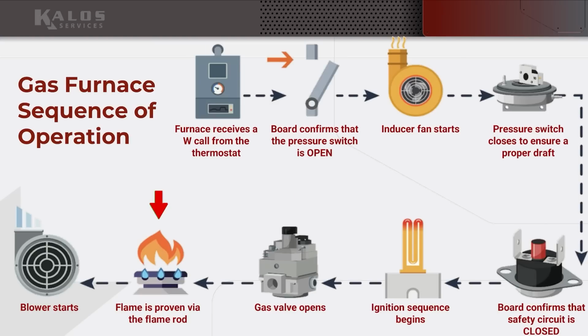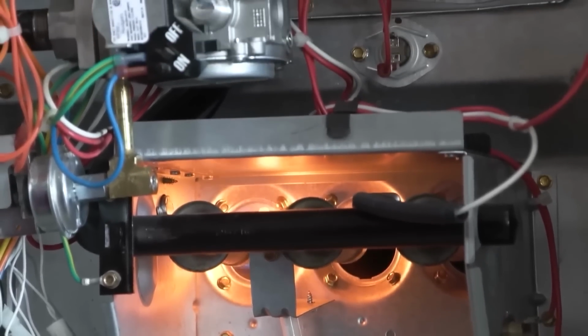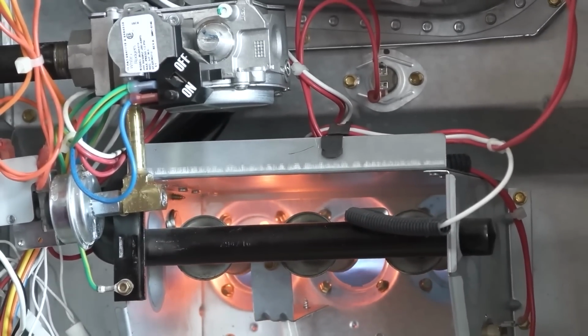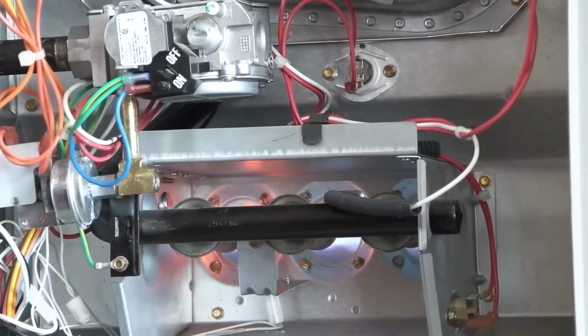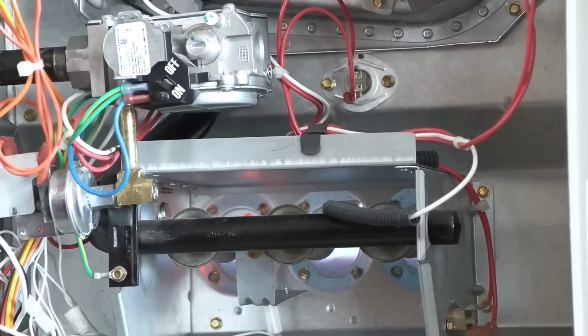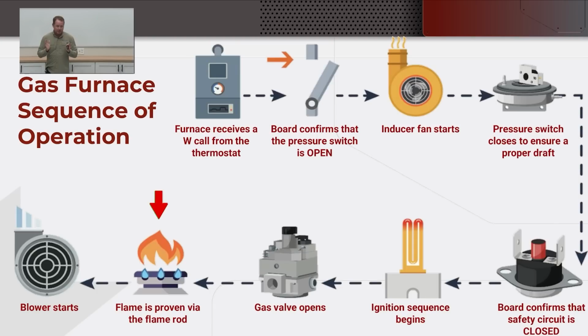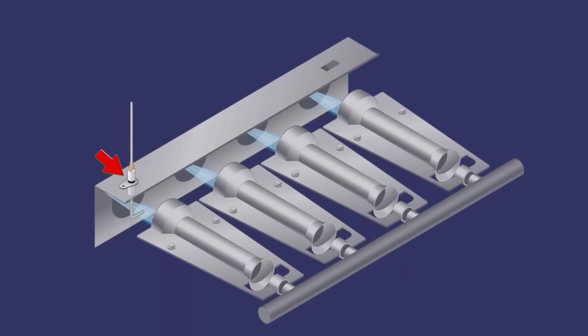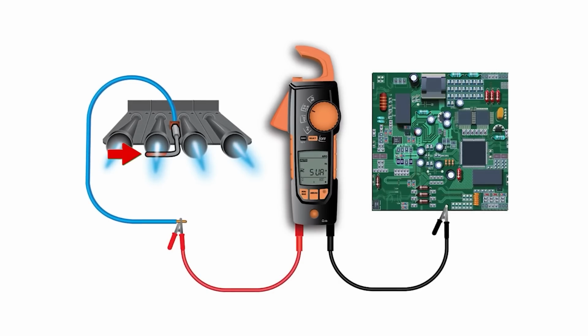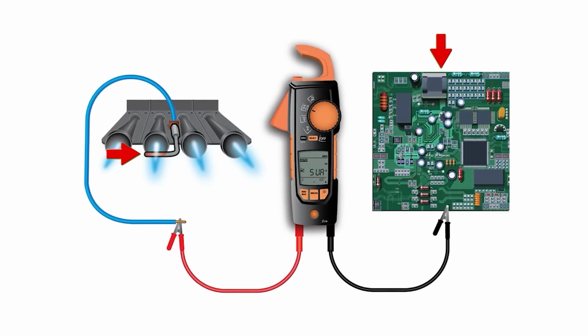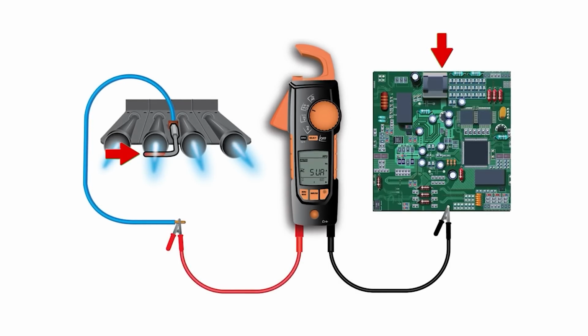Then it proves flame, and this is where I really want to end here, because this is the part that just blows everybody's mind. This is where it goes wrong a lot. In order for a furnace or a pool heater or whatever to prove flame, it has to be well grounded. You have a flame rod, mostly. Sometimes it uses the igniter or some other strategies, but you generally have a flame rod. And that flame rod needs to be immersed in flame in order to connect basically from the board through to ground, and it can prove a current. And that current is a DC current, and that's why they call it flame rectification, to get real fancy.